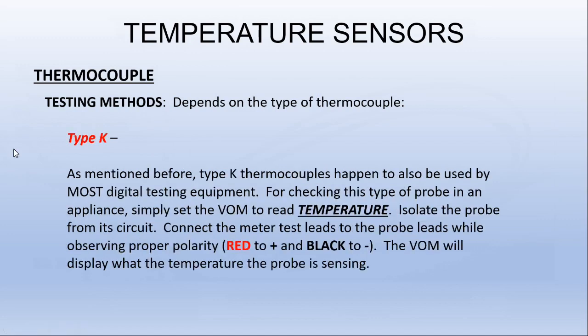The second type of thermocouple is type K. As mentioned before, type K thermocouples happen to also be used by most digital testing equipment. For checking this type of probe in an appliance, simply set the voltmeter to read temperature, the temperature setting on your voltmeter. Obviously, this would probably be a digital meter. Isolate the probe from its circuit. Connect the meter test leads to the probe leads while observing proper polarity, red to positive, black to negative. The voltmeter will display what the temperature is sensing.